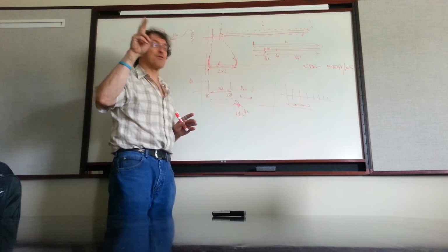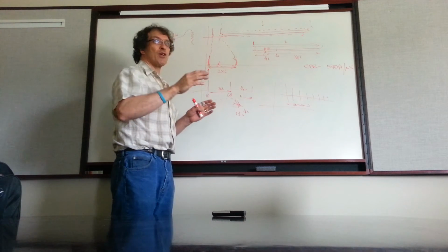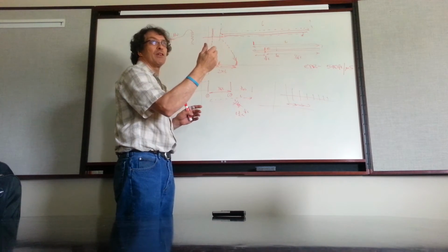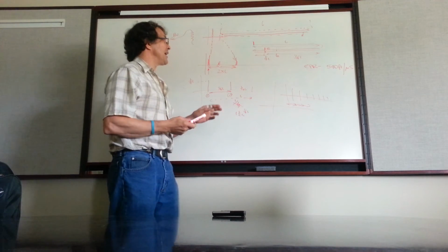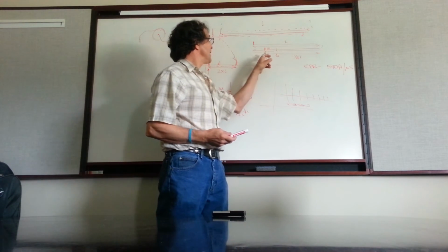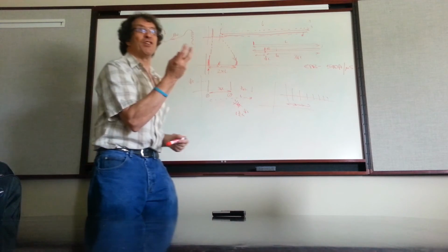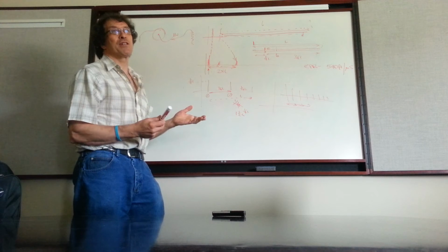It looks a bit confusing because you go, well, that's the longer distance, that's the shorter one. And if the top has power on it, why isn't the top the shorter distance? Well, it's realised that the pulse that's appearing here travelled from the fault backwards, not forwards. So it's inverted, and it always gives you the wrong impression when you first see it.